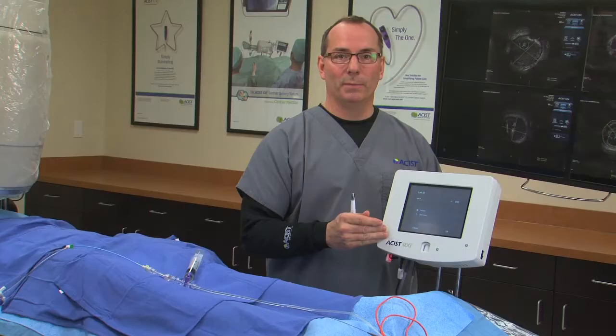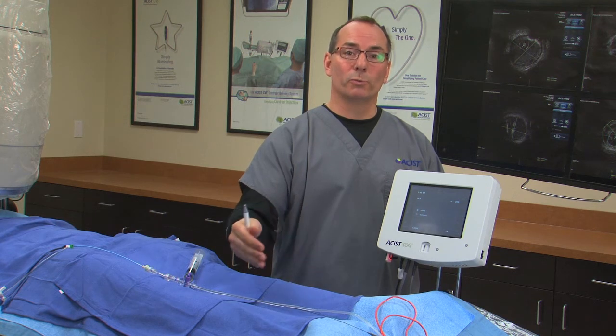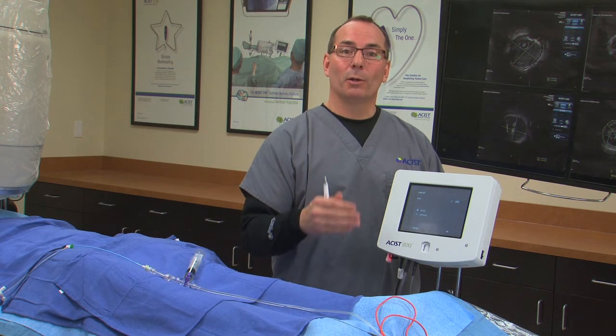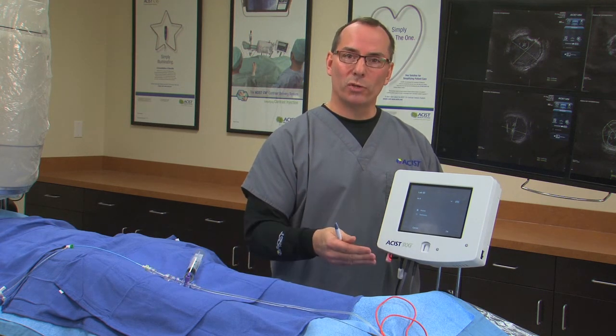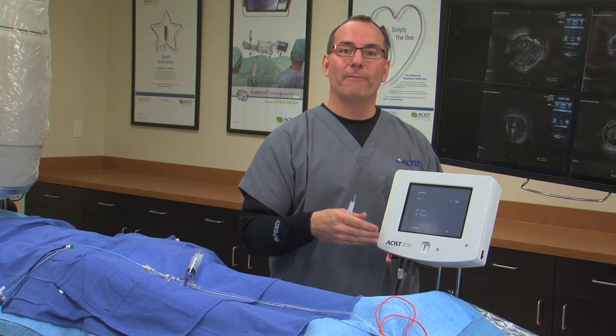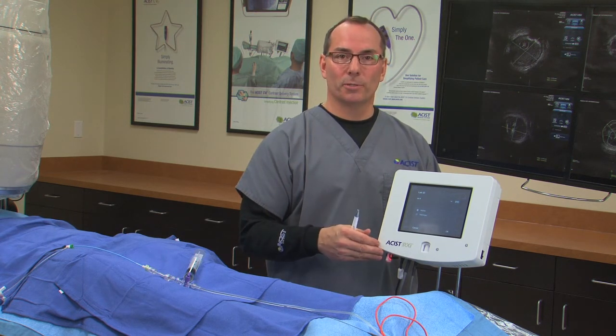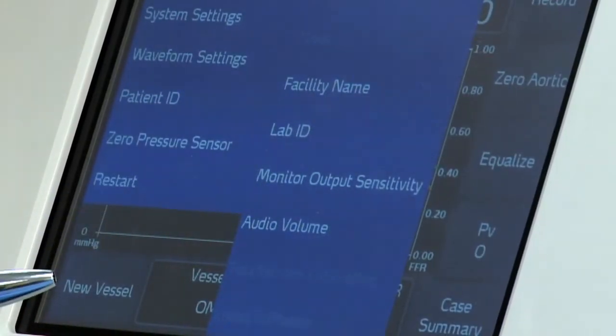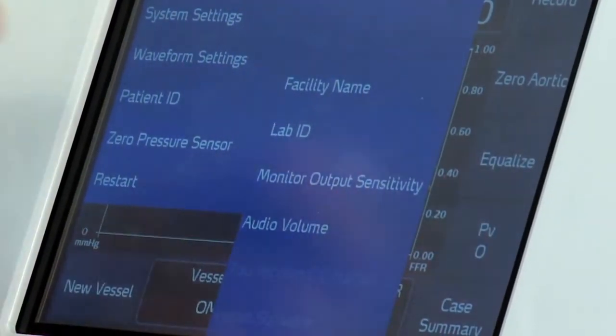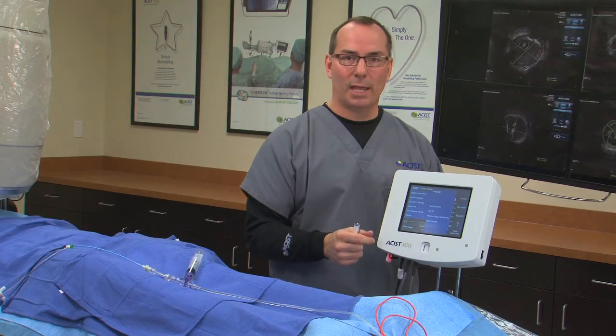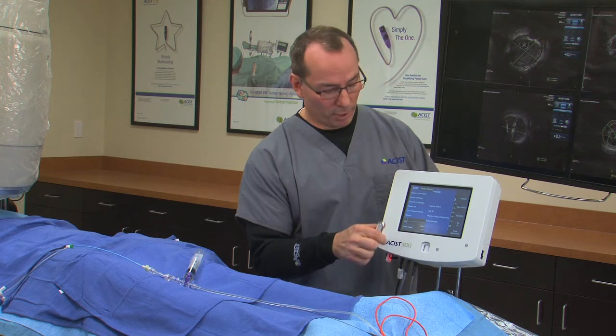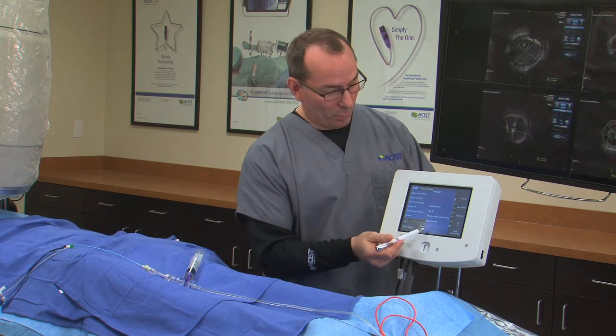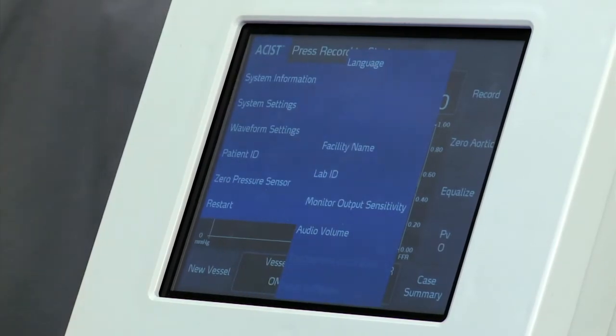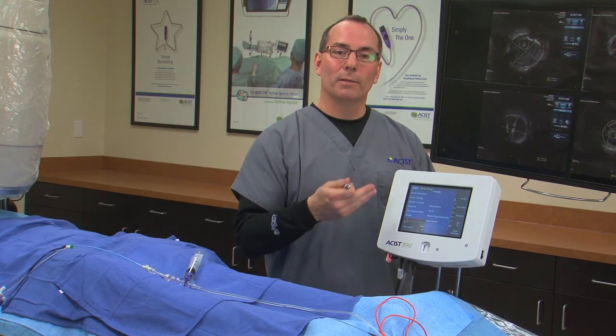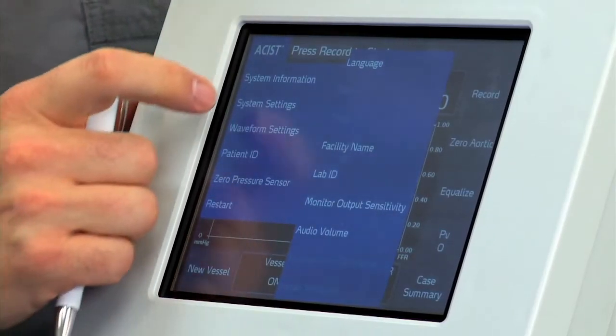If it is in the mobile mode, now we're telling the system that this will go from room to room, and it'll program the software to prompt the user to zero this system for every FFR procedure. Audio volume, also touch screen calibration if the touch screen calibration becomes uncalibrated. And then finally, we have a submenu down here for installing software for making the system upgradable.